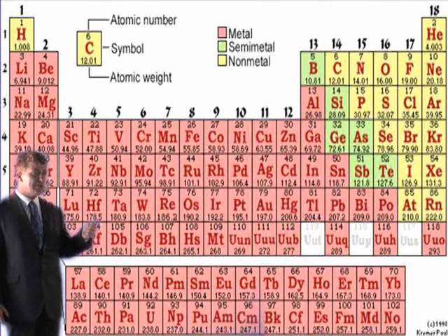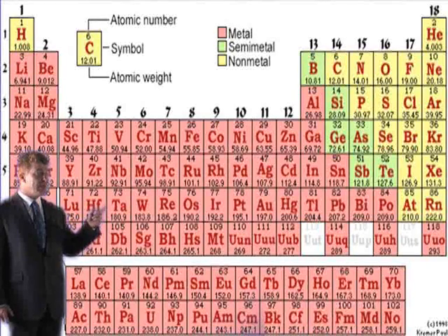One more. Is acetylene heavier or lighter than air? C2H2. Well, carbon's 12, hydrogen's 1. That makes it 22, 24, gives you 26. Acetylene is lighter than air, but only slightly. Air is 28.8, acetylene is 26. In other words, it's going to mix very, very well. And it's a very volatile gas, is acetylene. So where should you store acetylene cylinders? Outside, in cages, well ventilated, away from buildings, away from ignition sources.